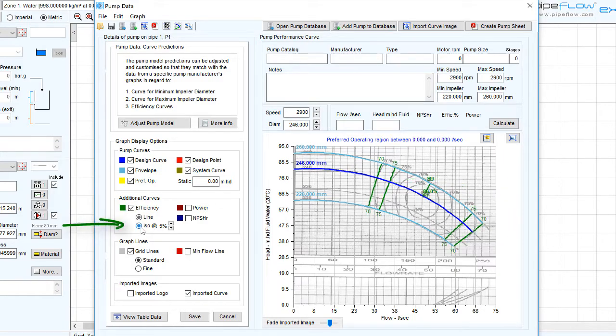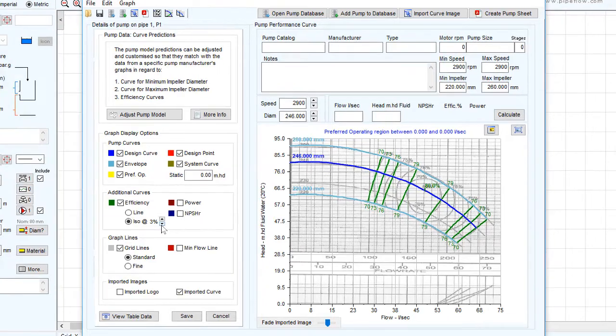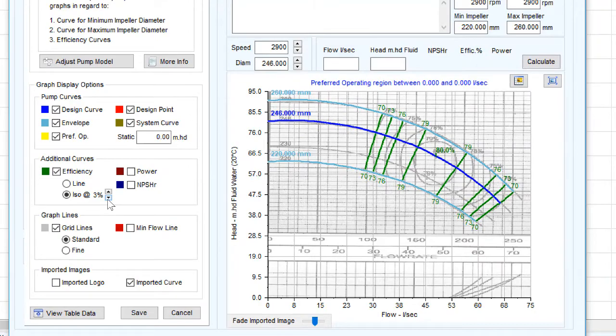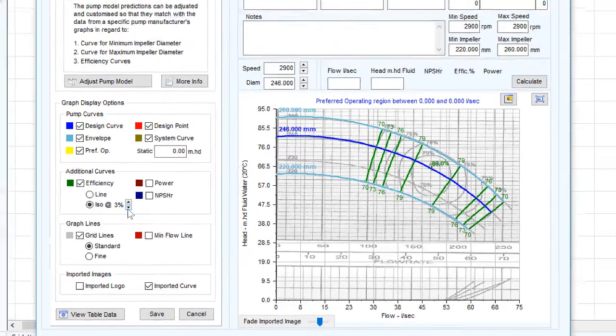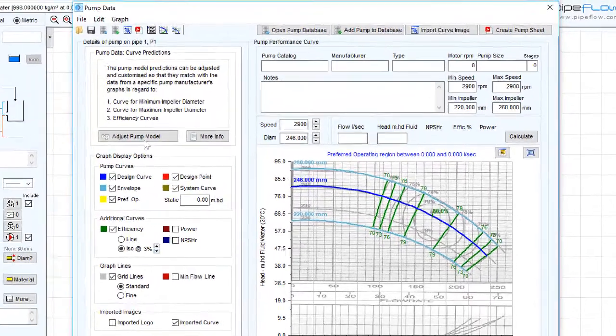We can click Graph Options to display the efficiency data on the graph as a series of ISO efficiency lines that show the efficiency performance across a range of impeller sizes. Initially, the pump's predicted performance is based on the standard affinity laws, and often the predicted performance curves will agree closely with the pump manufacturer's published graph.